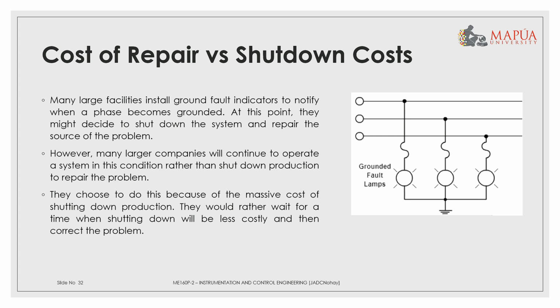Many large facilities install ground fault indicators to notify when a phase becomes grounded. At this point, they might decide to shut down the system and repair the source of the problem. However, many larger companies will continue to operate a system in this condition rather than shut down production to repair the problem. They choose to do this because of the massive cost of shutting down production. They would rather wait for a time when shutting down will be less costly and then correct the problem.